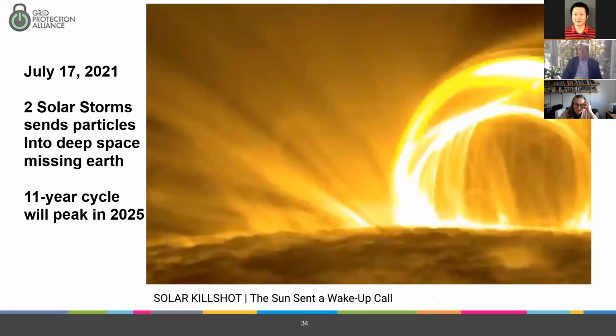Either one of those storms were comparable to the Carrington event of 1859 that melted telegraph wires and caused a lot of damage to the system, long before Edison's Pearl Street Station. The point is we will have solar events. They will damage equipment, primarily due to the DC source that overexcites transformers, causing generator and transformer issues following a severe electromagnetic storm from induced DC current.